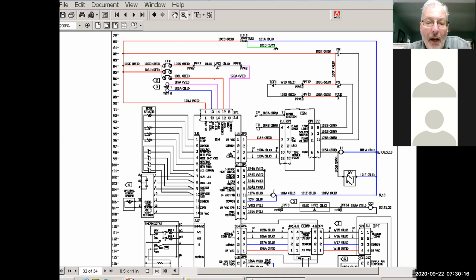This is kind of a layout of a Reliatel system, and we talked about this earlier. If you look at the transformer, we take 24 volts from the transformer and go right to pin 1 on the board. So we feed that directly to the board. Pin 1 is always going to be the red wire. So if your light's not on the board, the first thing you probably want to do is go right here and check for voltage, see if the transformer is working. If I have power here and my light's not on the board, on the older boards you had a fuse that you could change. On the newer boards, it means the board's bad or you got a bad connection. So before you go too far into it, just look for power right here.